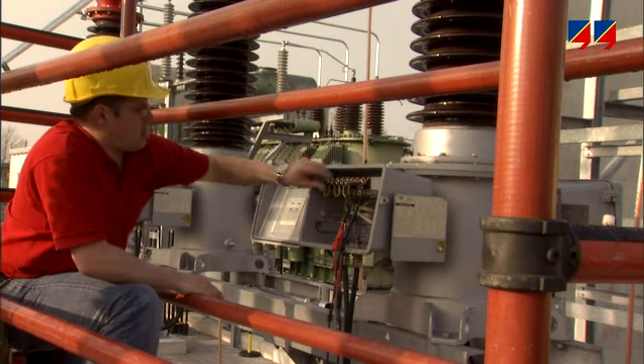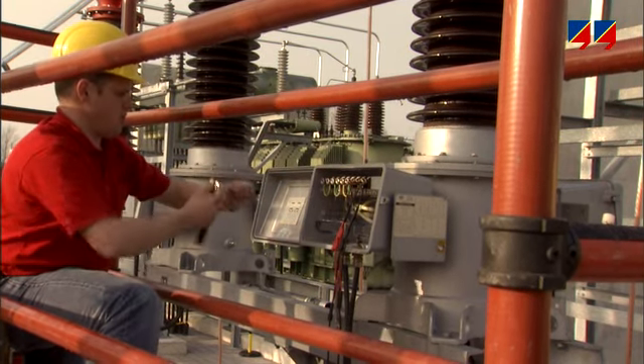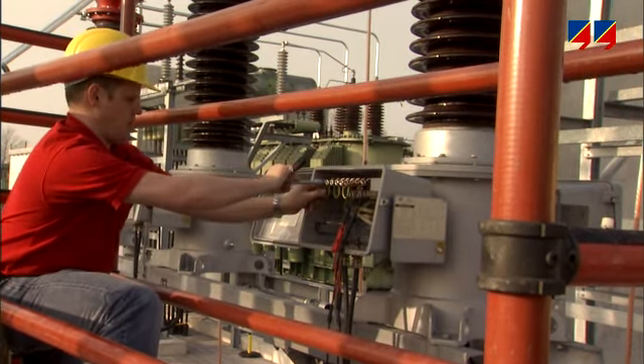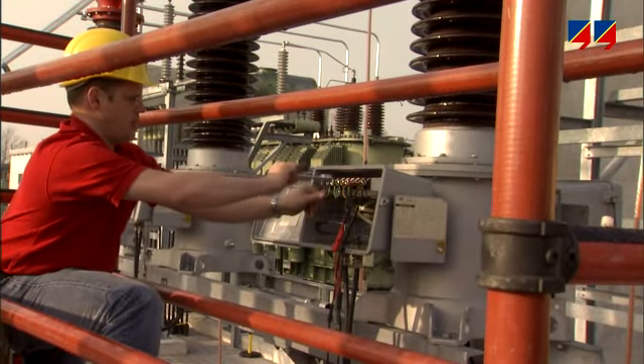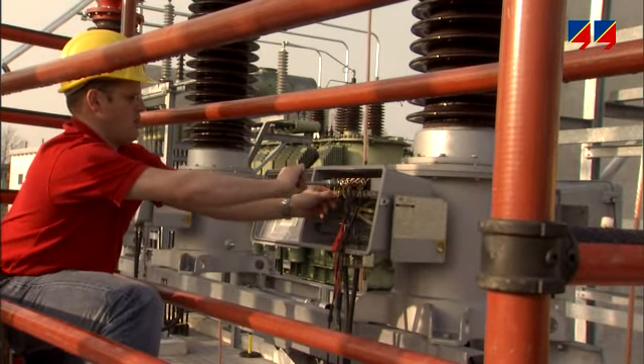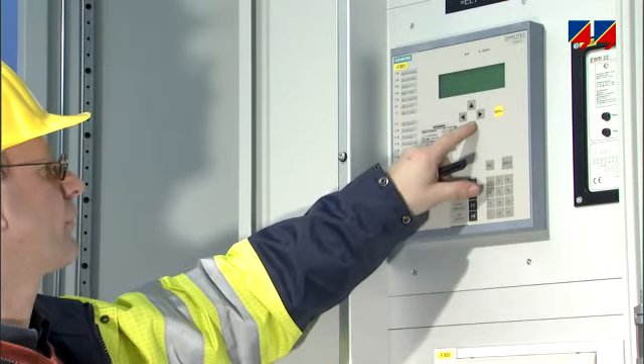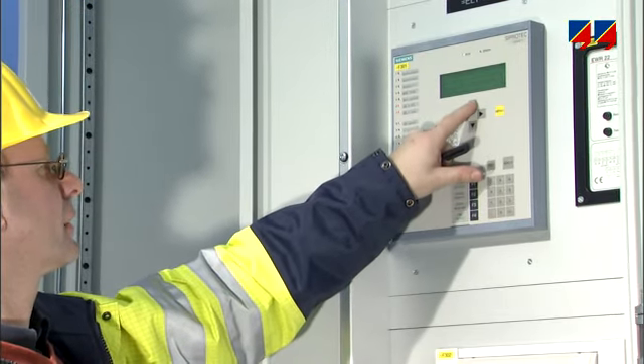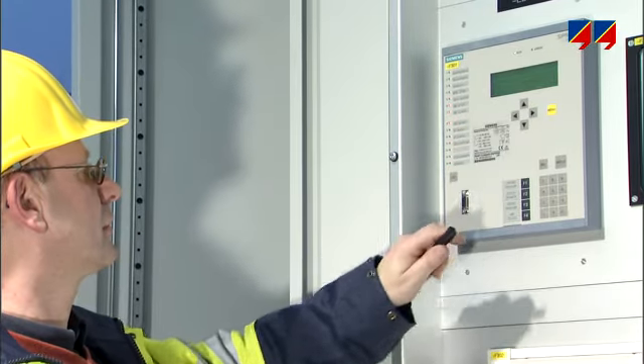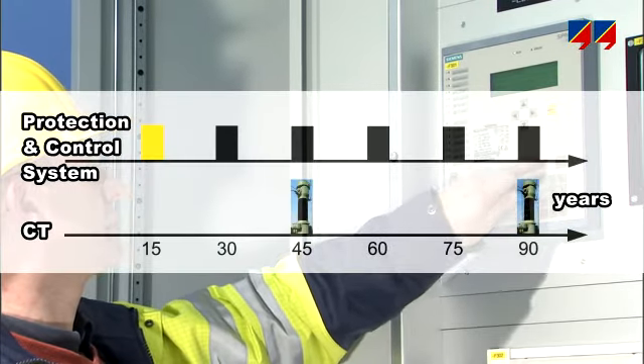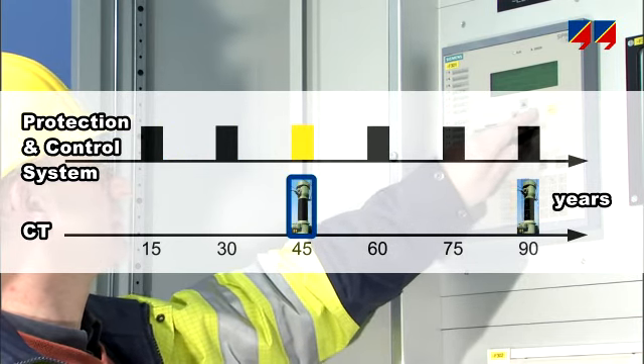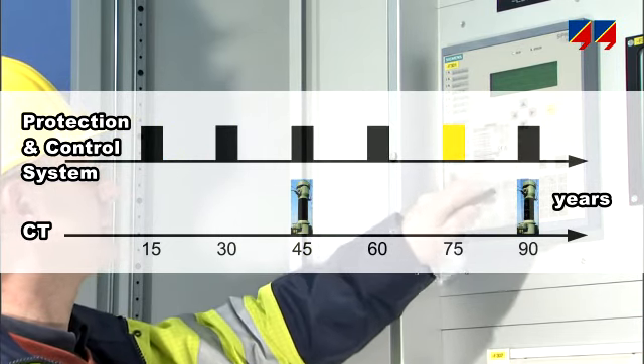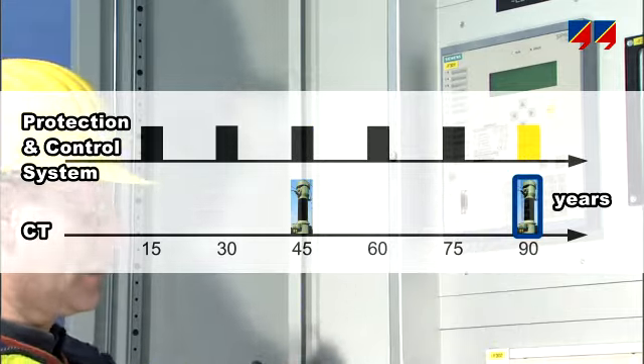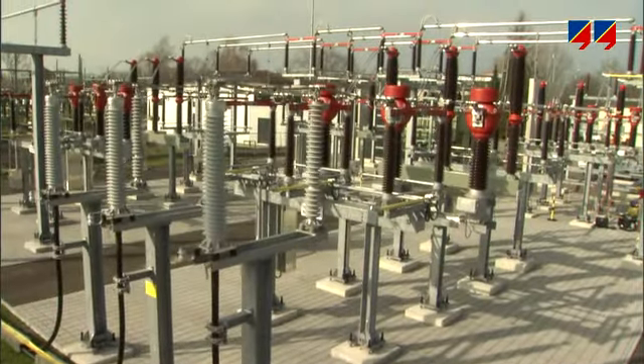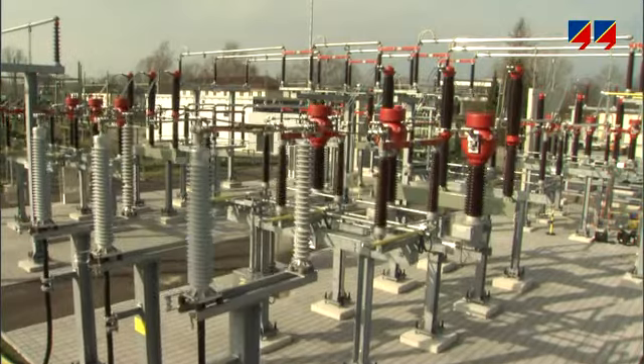After shipping and installation, commissioning engineers check the wiring and verify that the CTs will perform correctly in the plant with the actual operating burden. CT circuits are rechecked when a plant is modified, for example, when new protection and control systems are installed. These systems have shorter life cycles than a CT, so such changes may occur several times during its lifetime. In some countries, it is mandatory to regularly recheck the accuracy of metering CTs to ensure correct billing.